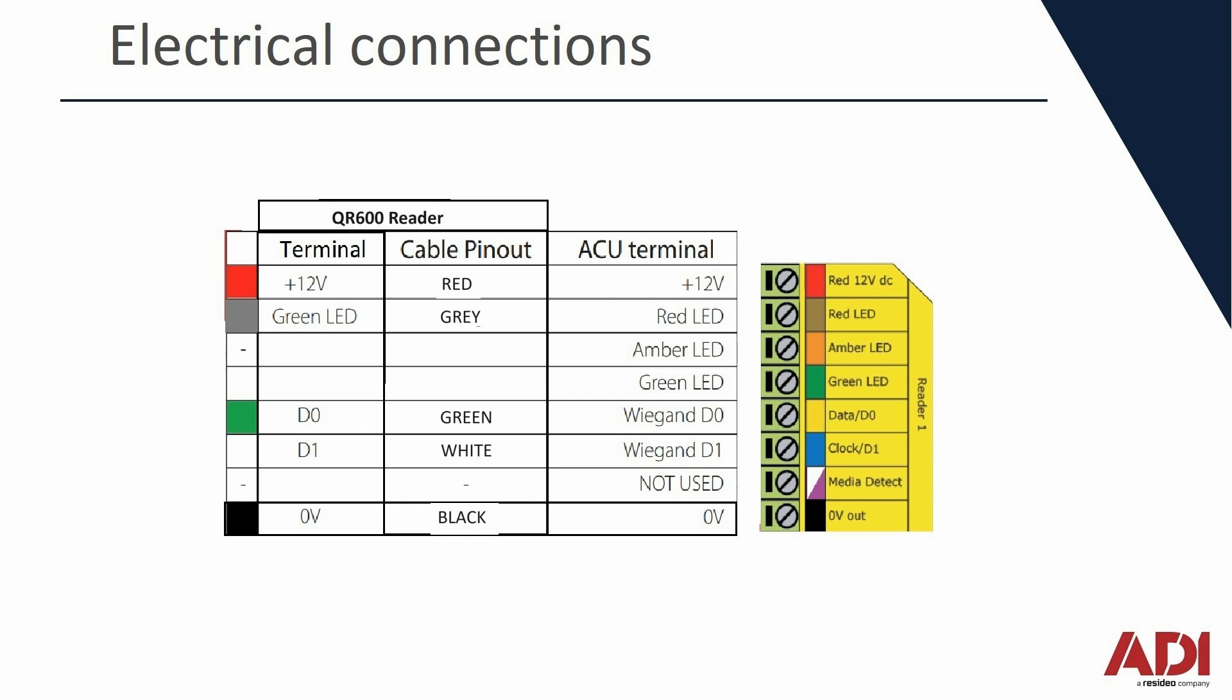So let's have a quick look at the electrical connections. It's a five wire connection so you'd use a three pair cable: red and black for power, red first, grey for the LED control, we're going to set this up as an OEM reader, and then green and white for data one and data zero.